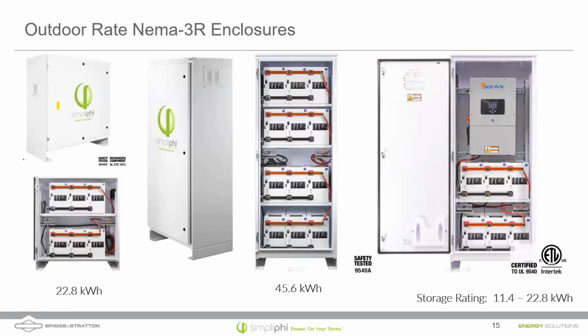So if we're discharging at a recommended C/2 discharge cycle, the battery cell temperature will rise during that discharge cycle. And so if you were able to maintain a temperature really low, the batteries wouldn't go through a full discharge cycle because of the increased internal resistance at low temperature. But typically, and I was just talking last week with our lead engineer about this, the battery temperature typically rises up towards about 20 to 25 Celsius, even in cold ambient conditions during a discharge cycle. And so what that means is that we get very close to 3.8 kilowatt hours out of the batteries, even when they're discharging at 0 degrees Celsius temperatures.